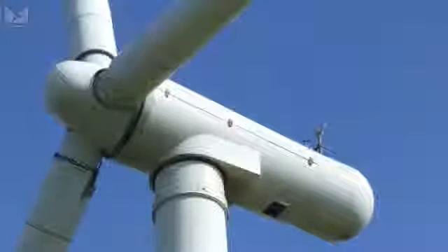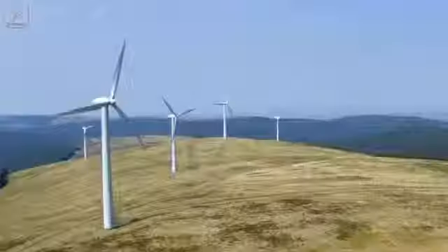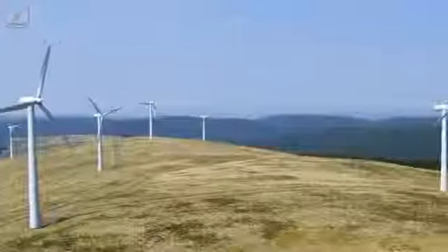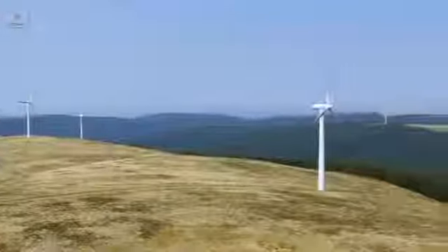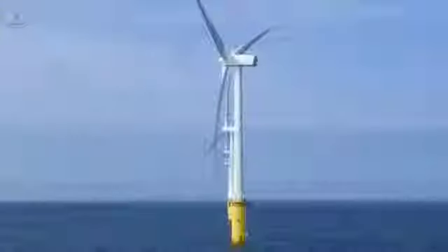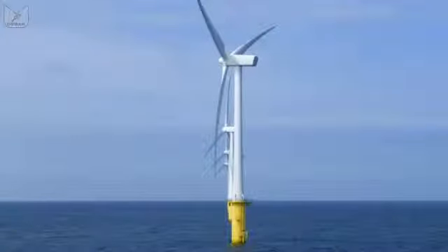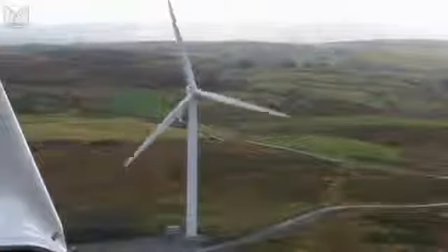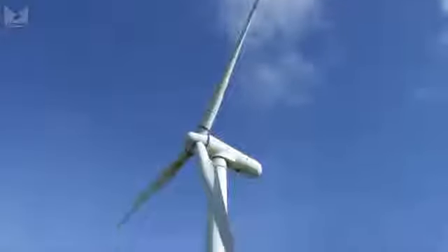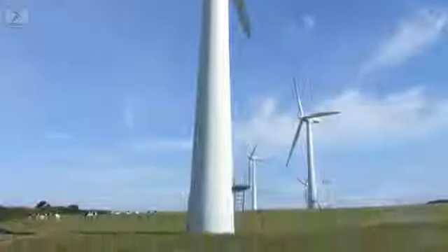And in this nacelle we have the generator, often a gearbox and occasionally a high voltage transformer, and the whole thing sits on top of a tower which is mostly there to keep the blades from digging a hole. We tend to class turbines by their power output, and hence their physical size. Wind farms might use many sub-megawatt turbines, each producing 400-600 kilowatts each, or a few multi-megawatt turbines producing maybe up to 3 megawatts per unit. Apart from physical scale, they are arranged a bit differently, so let's start by looking at a typical sub-megawatt model.